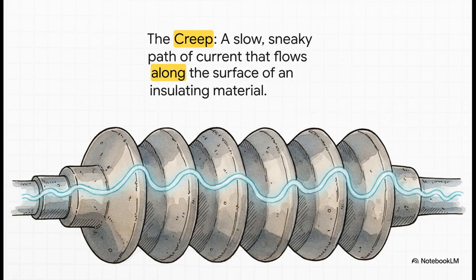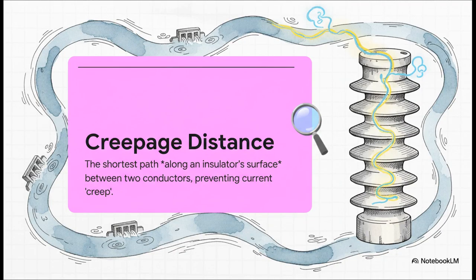If the first escape route is a dramatic jump, the second one is much sneakier. It's not a leap, it's a slow, persistent creep of current along a surface. This sneaky path is blocked by a principle called creepage distance. Think about spilling water on a countertop. It doesn't just stop, it finds a path, it'll snake around things. Electricity does the exact same thing along the surface of an insulator. So to stop it, engineers make that surface path incredibly long, often by adding ridges and fins, to literally make the journey too far for the current to complete.